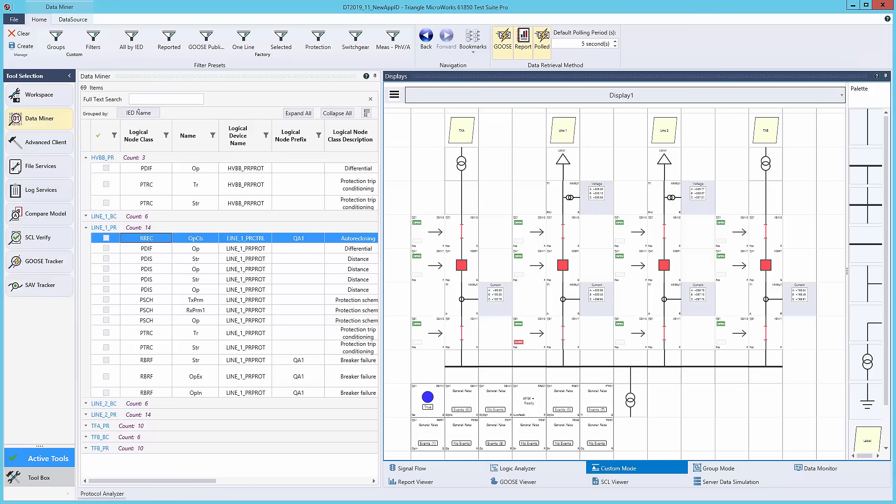I will trigger the breaker failure event in the simulated substation from DTM. When the event is finished, you'll see all the breakers open to prevent energy loss in the substation. You'll also see any other signals being sent in the data cache below the single line diagram.